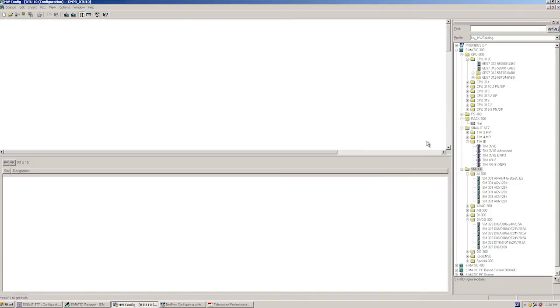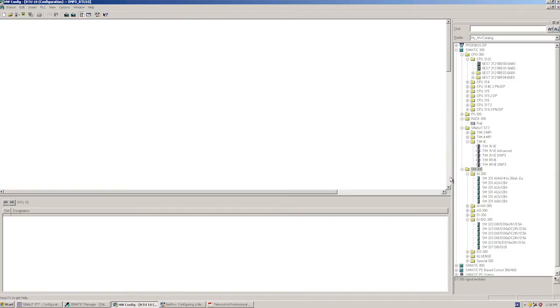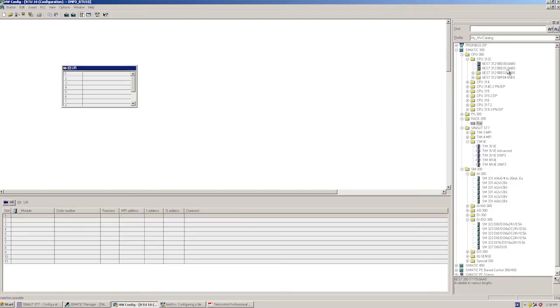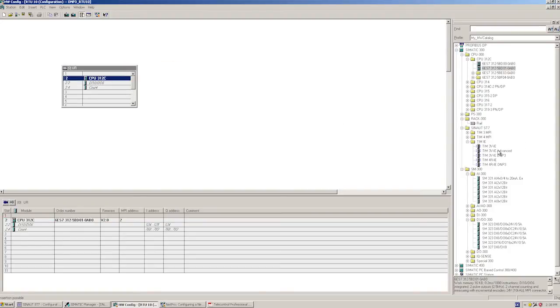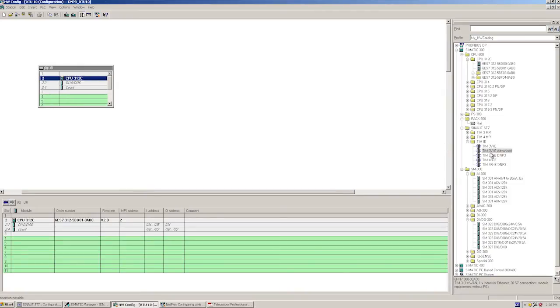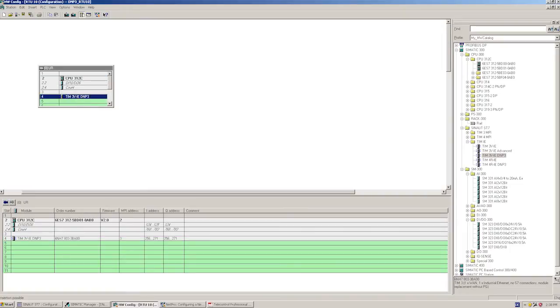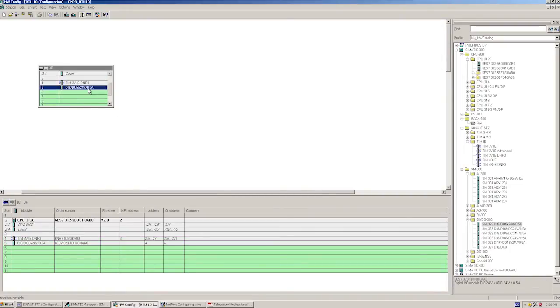We now configure our RTU in hardware config according to our hardware setup: an S7 standard mounting rail, a CPU 312C, a DNP3 TIM module, the digital input output module of our simulation module, and the analog input module.